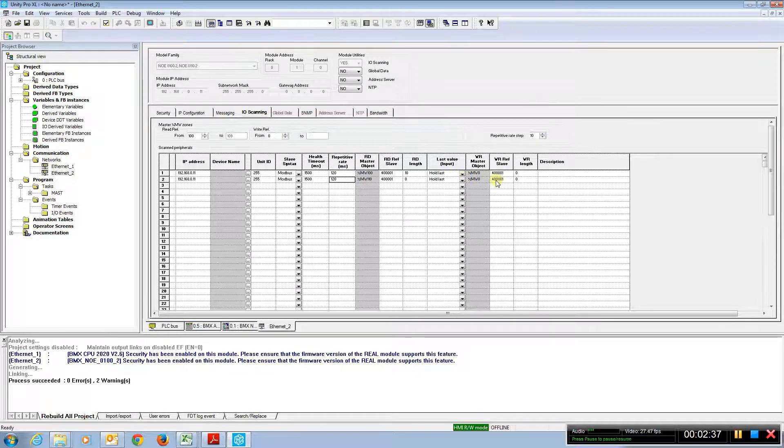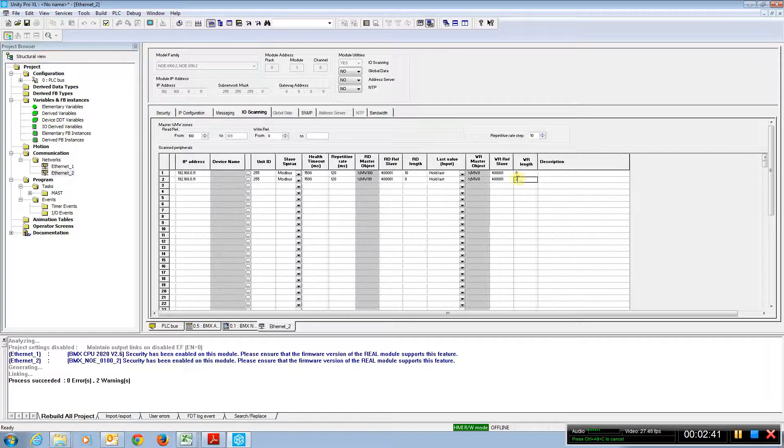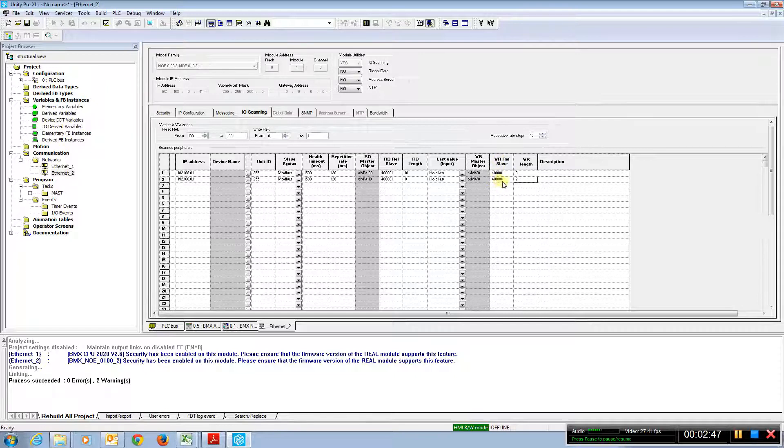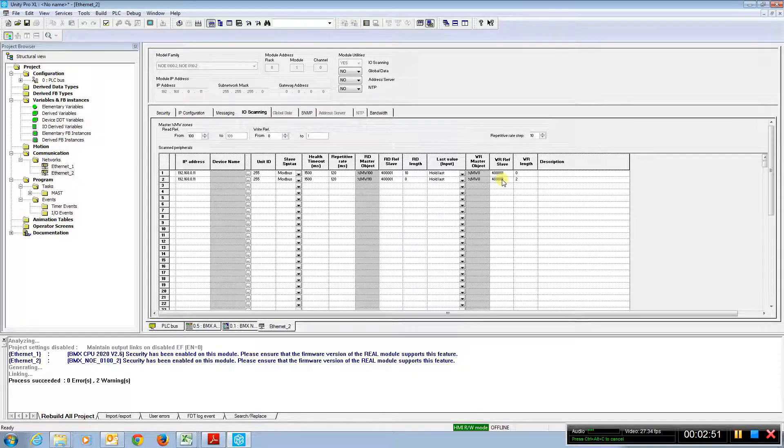We'll leave zero for the read length here now. And what we'll do is for the write length, we may put something like registers, two registers. And in this case, we may not want to write to the slave at 40,001. We may want to write at some predefined number, 40,050.